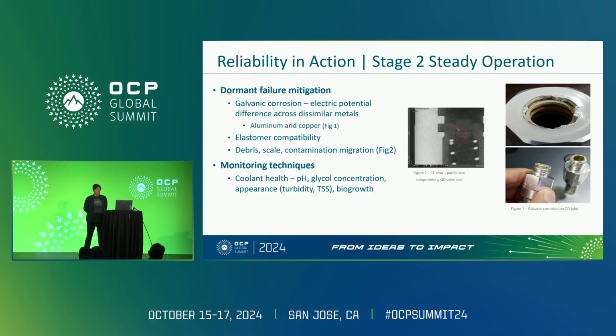There's really a lot of different corrosion mechanisms, though, that we need to take into account for liquid cooling. The example I want to point to here is galvanic corrosion, where we've got a difference in electrical potential of the materials in the system. Here we have an anodized aluminum connector threaded into a copper or brass fitting with some deionized water flowing through it, and lo and behold, we've created a battery. The aluminum QD works as a sacrificial anode and has catastrophically failed at the thread. In order to avoid that, we should certainly be looking at different material interactions and compatibilities. But the point I want to make is if we had done salt spray testing on that single anodized component, we might have had an indication it would last.